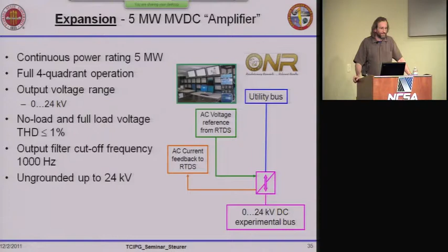It also makes a lot of sense for offshore wind turbine collector systems, since most of them have variable speed capability and therefore an intermediate DC bus. Right now we are procuring and installing a 5 megawatt, fully bidirectional DC capability that can act as an amplifier for our RTDS simulation, to conduct research, testing, evaluation, and model building for DC systems. Our target is 24 kV DC, and modularly we can accommodate 5 megawatts at 24 kV, 12 kV, and 6 kV. Those are the expansion plans.